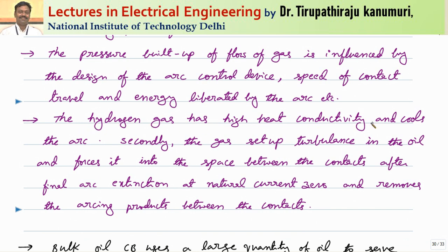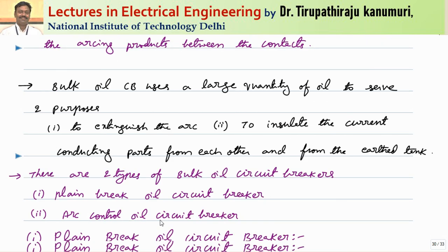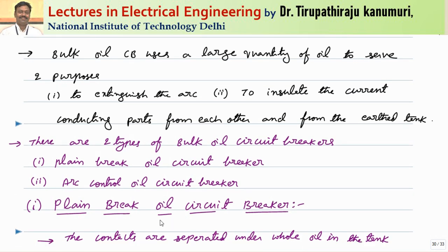The hydrogen gas has high heat conductivity and cools the arc. Secondly, the gas sets up turbulence in the oil and forces it into the space between the contacts after the final arc extinction at natural current zero, thereby removing the arcing products from the contacts. This bulk oil circuit breaker uses a large quantity of oil — that is why it is called a bulk oil circuit breaker. It serves two purposes: first, to extinguish the arc; second, to insulate the current-carrying parts from each other.